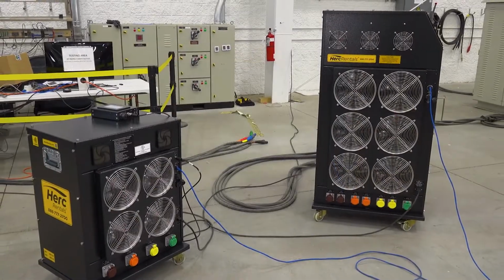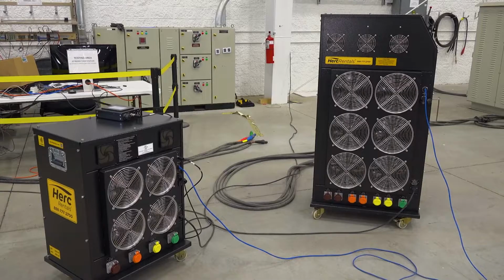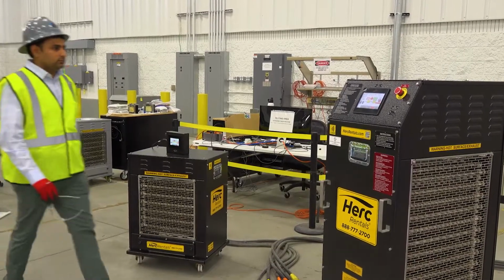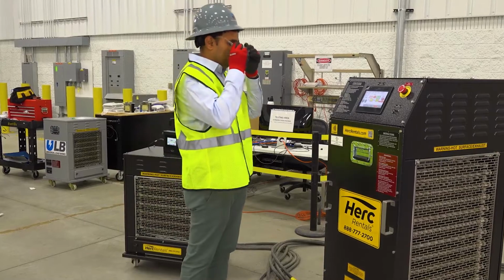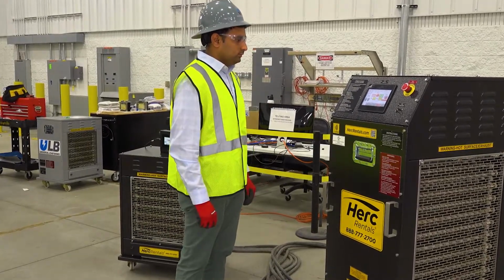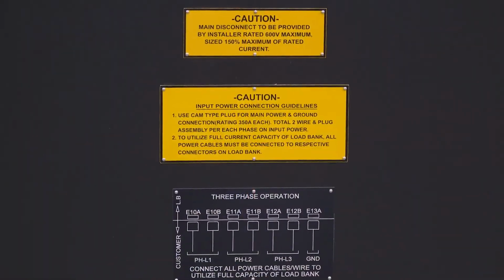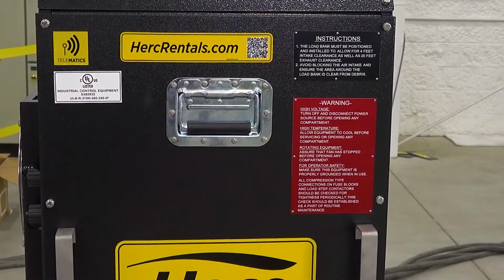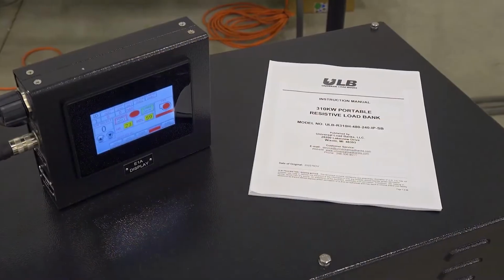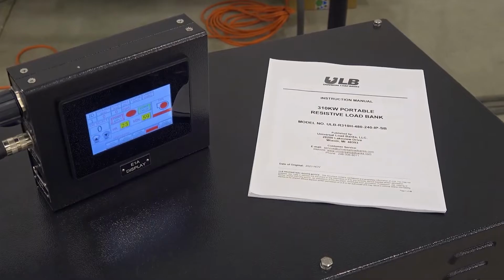ULB load banks are designed to the latest safety standards. However, load banks absorb large amounts of electrical current and user safety is paramount. Hearing and head protection, along with a proper reflective vest, are the minimum PPE required for load bank operation. ULB equipment is also labeled with cautions and warnings. The instruction manual will also detail the cautions and warnings of the unit.